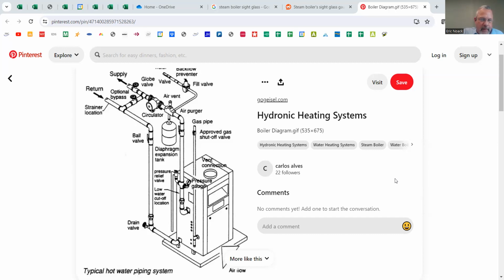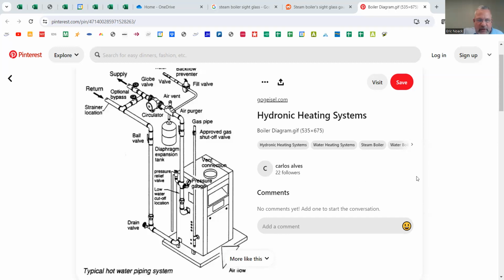It's got to be a secondary source that creates the steam, I would imagine. No, so it's a similar boiler, and they can look very much the same. In fact, some boilers are capable of being either steam or hot water. Some boilers can do both, right? I think, Eric, the steam boilers look like the old radiators for one, but I think they also have a relief valve on them, don't they? Well, there's going to be pressure relief valves on any boiler, okay?